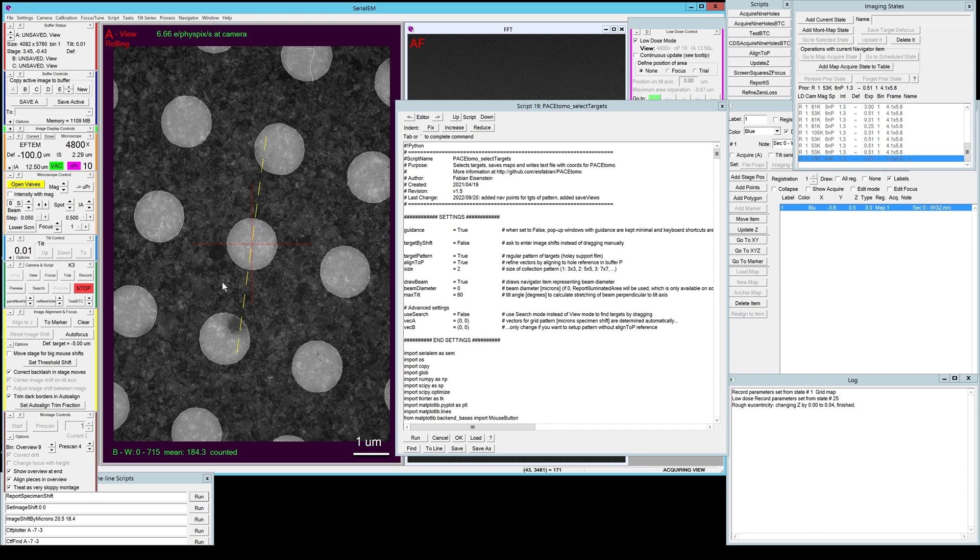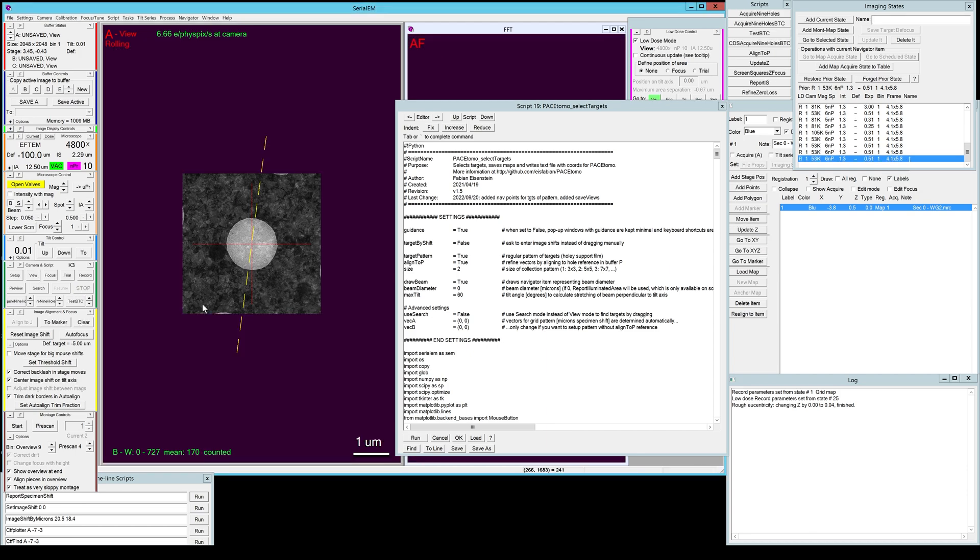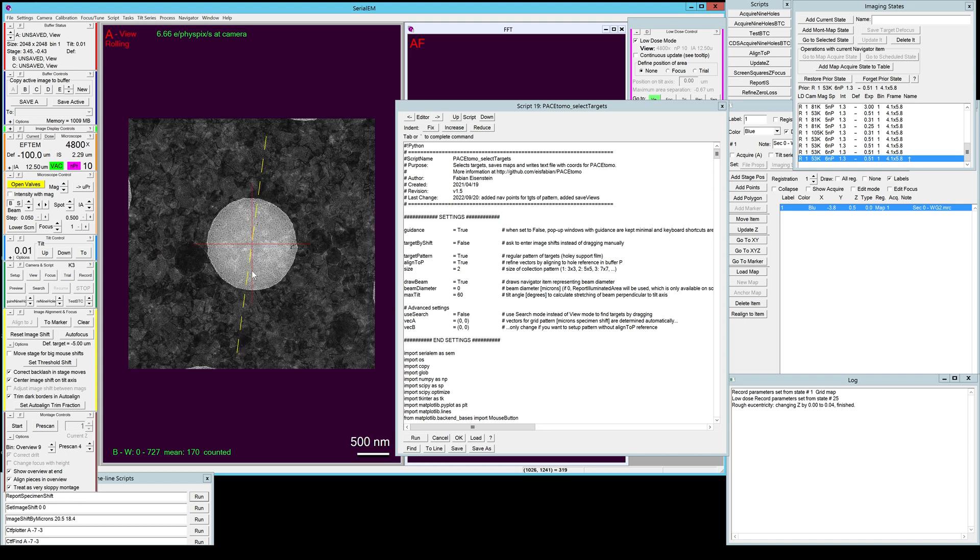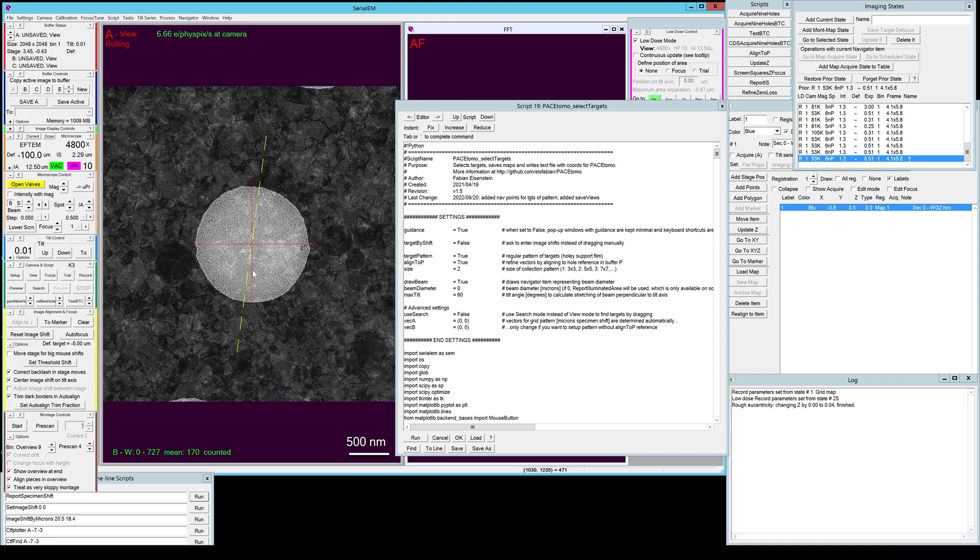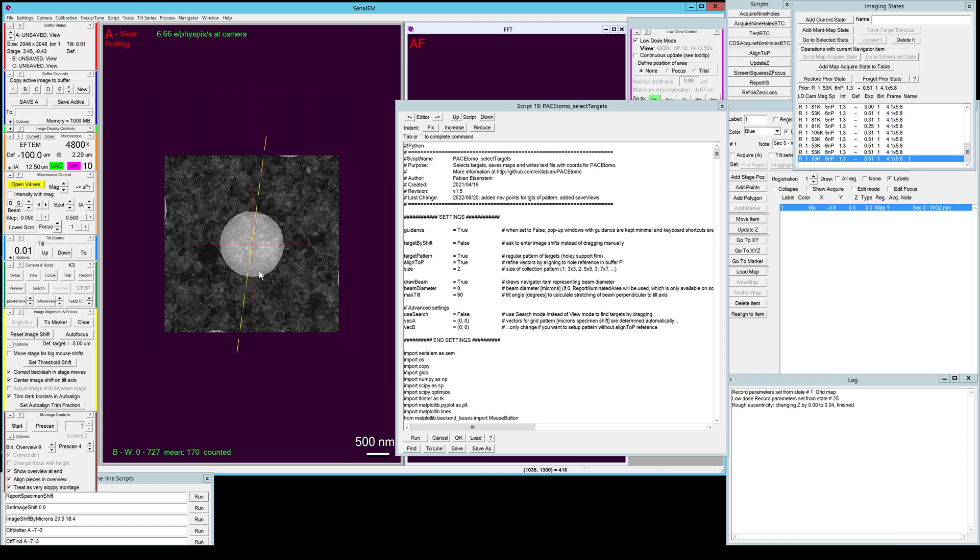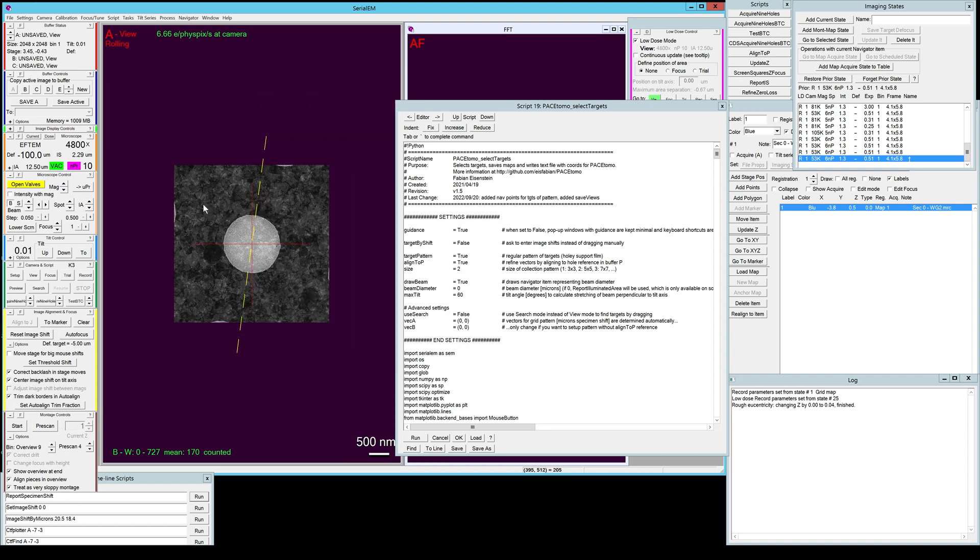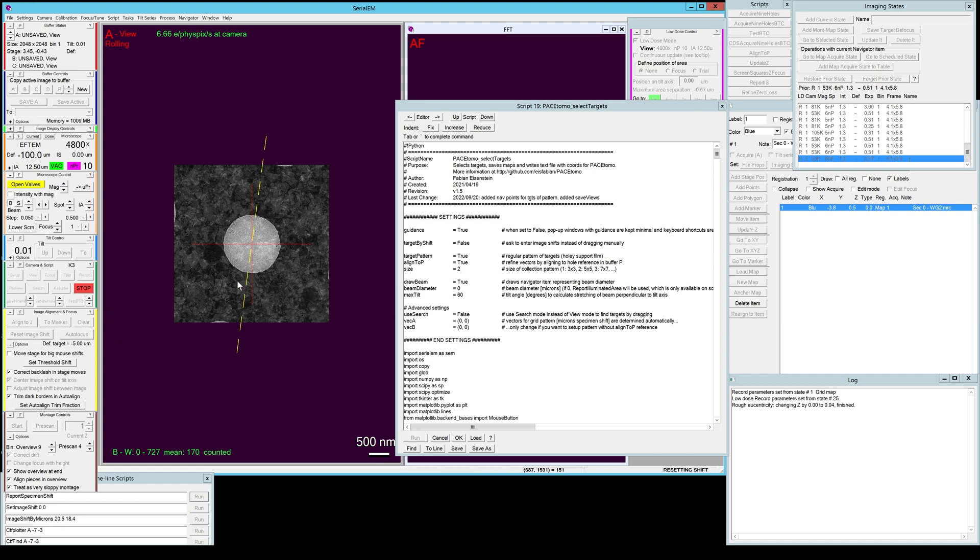Let's take another image and see if this is enough. You can see you barely see the edge of the other holes and by the looks of it it's already nice and center so we're just gonna save this image in buffer P. Since we also want to make this hole our center let's just reset the image shift so it will move the stage to this hole roughly.